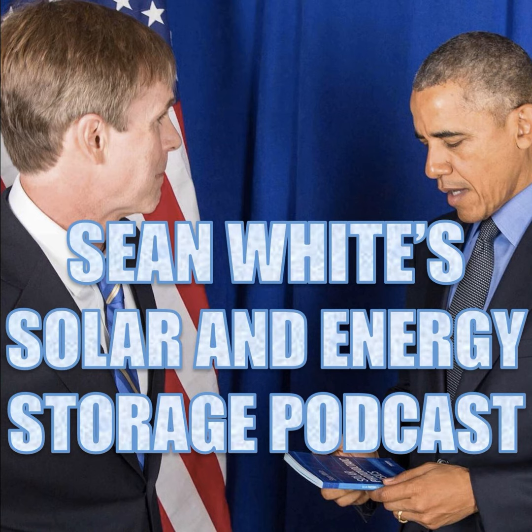So let's say that you had a 100-foot wire run and 10 feet of that was going outside. Well, that's 10%, and it also happens to be 10 feet. So you don't have to worry about that 10 feet that's going outside because it's 10 feet or 10% or whatever is less. And of course, this also goes for the 2020 National Electrical Code. So that's sort of like a little exception you have there.